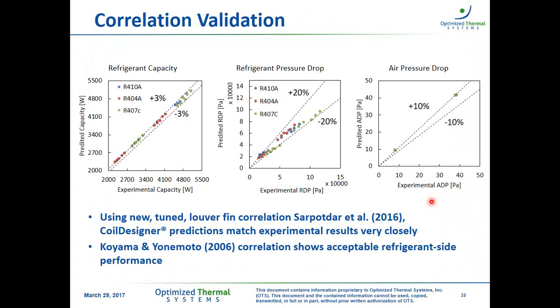Now, the importance of correlation validation. Though we have the correlations, which give us very good guidance on which direction to go, we're still going to end up having to validate them once we have a new design. And this is just an example of a correlation validation where we tested the heat exchanger for a louver fin using the louver fin correlation and a small diameter tube correlation. In terms of capacity, we got a pretty good agreement, plus or minus 3%. The refrigerant side correlation for pressure drop predicted plus or minus 20%. But what is interesting is to see that the air side pressure drop was within 10%.